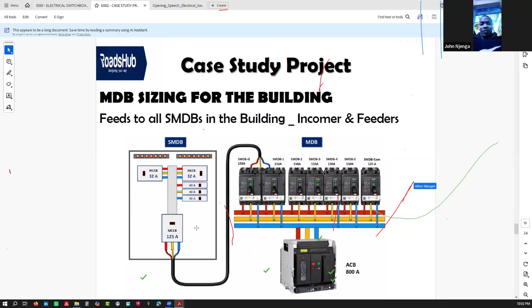And then you do the cable sizing for the transformer. And this one, I just want you to be sensitive because it's the last slide. So when you look at this cable sizing for transformers, you're now getting the transformer cable from the transformer to the main DB. We have an ACB of 800 amps. So you have a transformer that can handle up to 500 kVA. You do the full load current for that transformer, you get 696. But you need to include a derating factor.